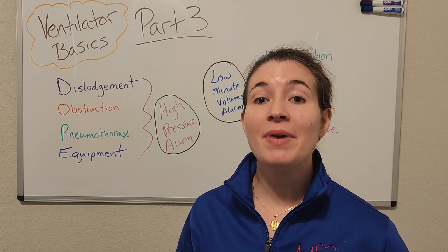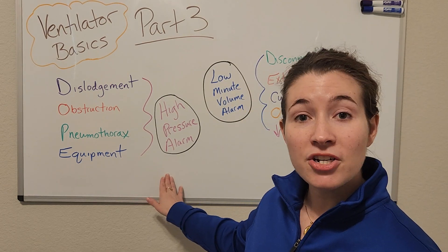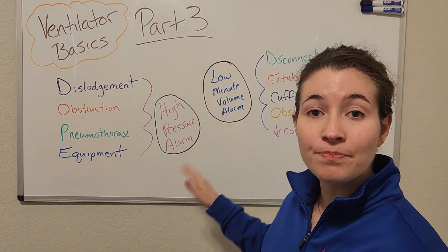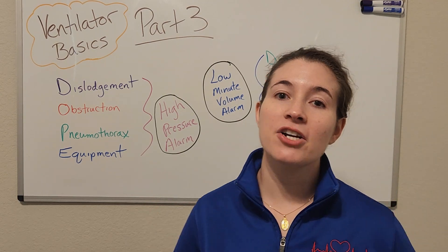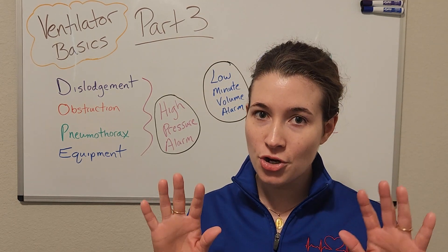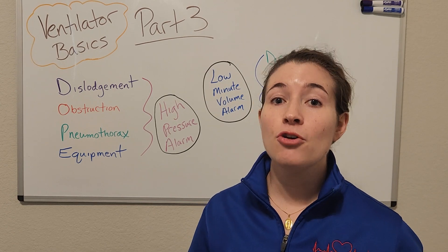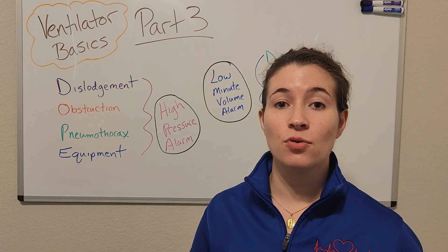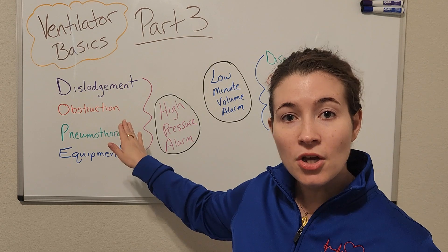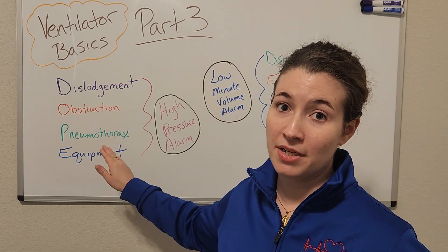The two main types of alarms you're going to see are high pressure and low volume. With high pressure you may have seen the mnemonic DOPE being used. DOPE stands for dislodgement, obstruction, pneumothorax, and equipment.